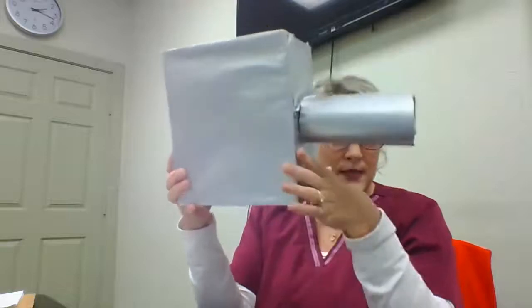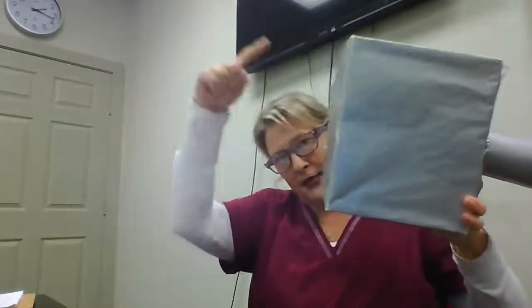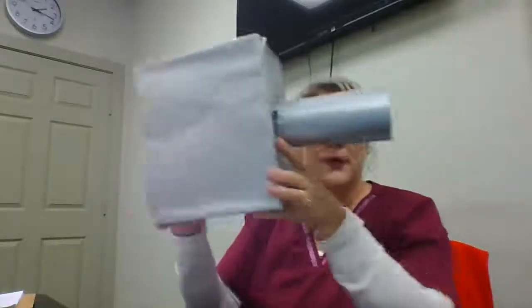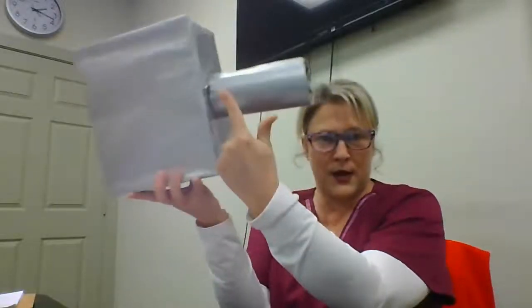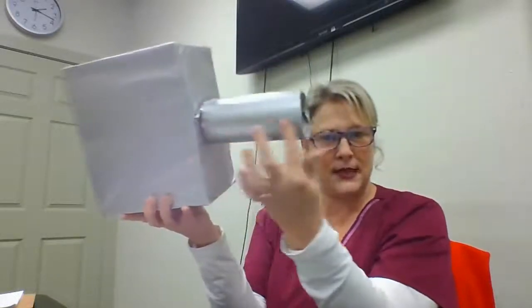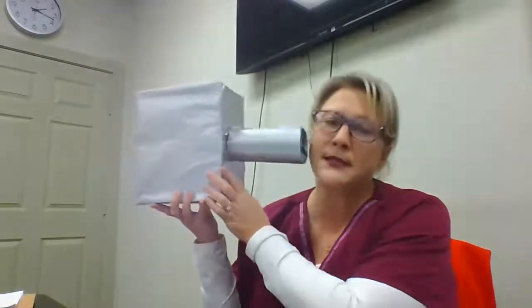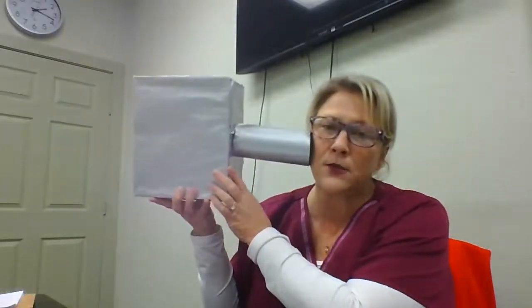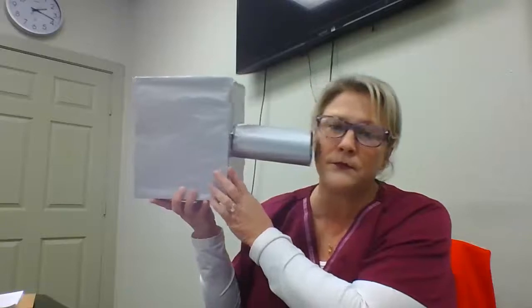So this whole thing is the tube head, right? And then it's connected to an extension arm, and then the control panels on the wall. So this little guy right here, this tubing, is your PID, position indicator device, because it positions the beam to where it's going to go to the film.